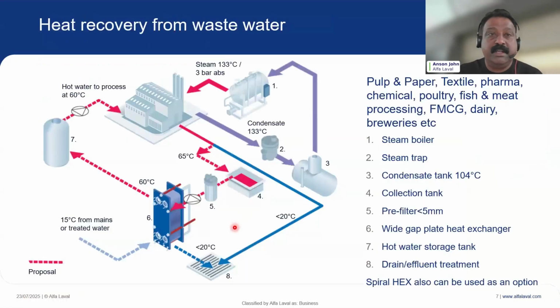Yeah, so heat recovery from wastewater. This is something which we do especially in the pulp and paper industry and also some beverage industry. So if you've got effluent which is high temperature water, like 60 degrees, 50 degrees C, of course, rather than wasting it into the drain, you can do a lot of heat recovery from that. And one of the biggest challenges the industry is facing when you recover heat from this effluent is that the particles present in the effluent can create some sort of fouling in the plate type heat exchangers.